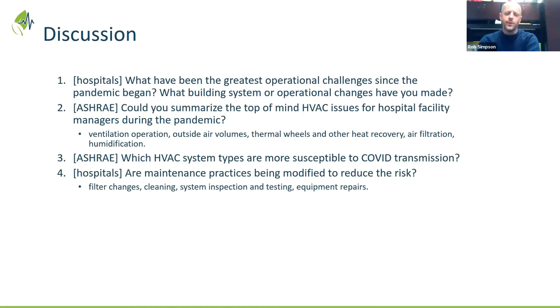We run our clinical fans 24/7, obviously. Clinical areas we run typically, just looking at my wall here, around 6 a.m. till 9 p.m., pretty much just Monday to Friday. The only systems we've really shut down through this — we have a big fan for our gymnasium that was off limits for a while, but we can get patients back in there now so we have that running. Our conference centers, we've shut all those air handlers down all weekend, so they're off from about 9 p.m. Friday until about 6 a.m. Monday morning. We haven't done too much shutting down of systems through this, because we still have a fair amount of non-clinical people in some areas, and they obviously need the systems Monday to Friday.